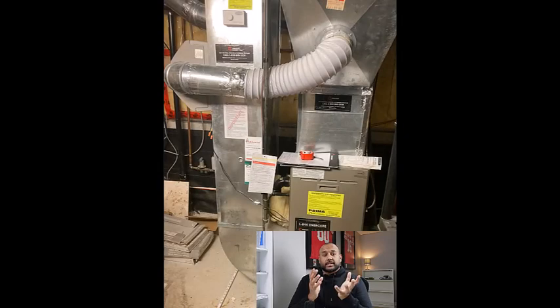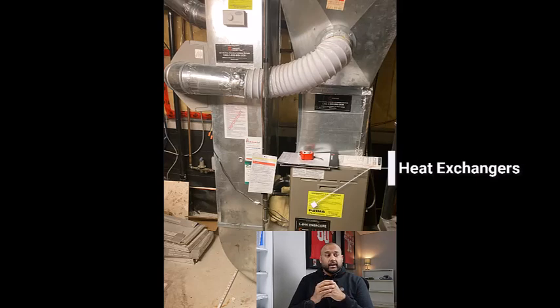The blower sometimes goes. That's repairable. However, in our case, that earthy smell that we were getting was actually high levels of carbon monoxide. So once the technician tested for that, he had to shut down the whole furnace because it was unsafe. One of the causes for the carbon monoxide to be leaking throughout the house was that one of the heat exchangers within the furnace probably has a crack in it. It's best to just replace the whole unit rather than repair that one, which would probably be just as costly. This was recommended by the technician.